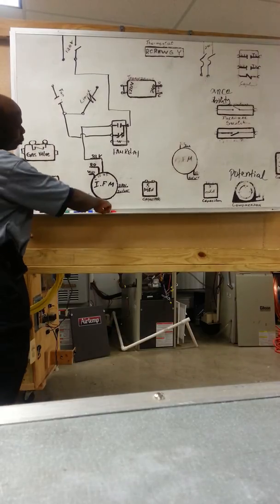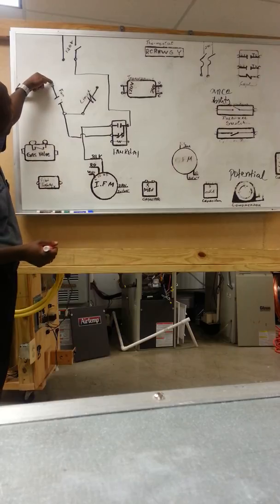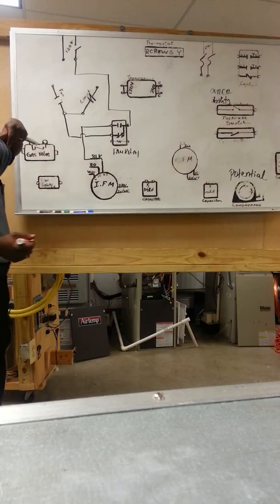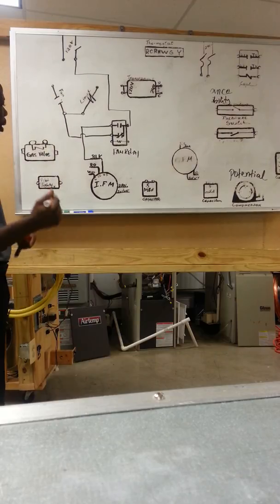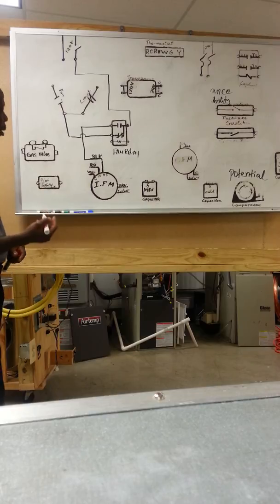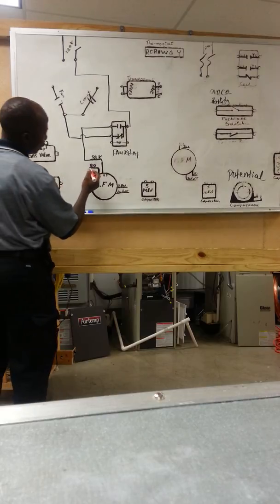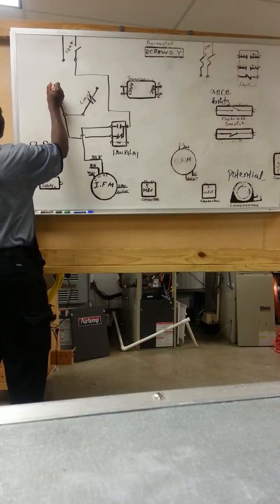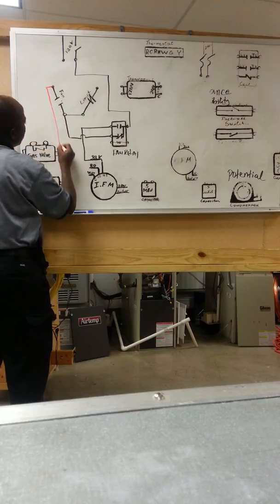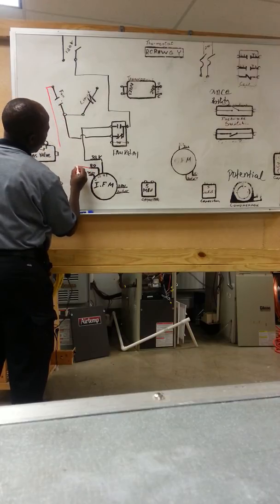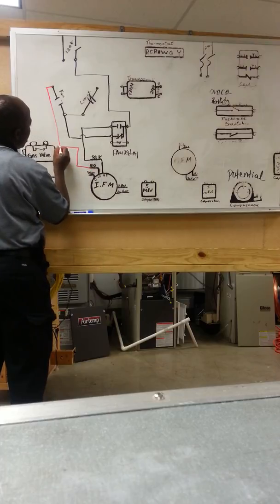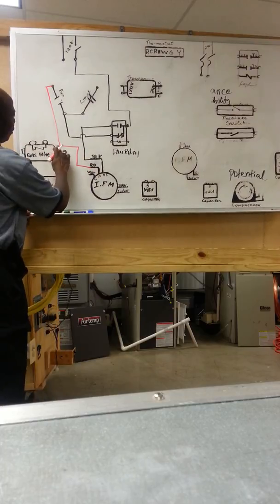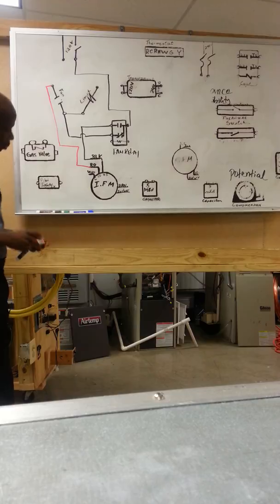So what we're going to have to do is get power from the top of the normally open fan switch on the fan center and bring it down to the low speed on the indoor fan motor, which is this red here. So we're going to use a red wire. Come down, red. Low speed for heating. We have the high speed for cooling.